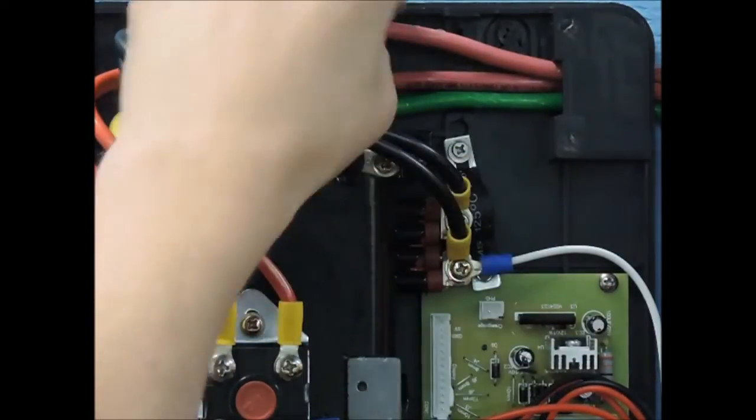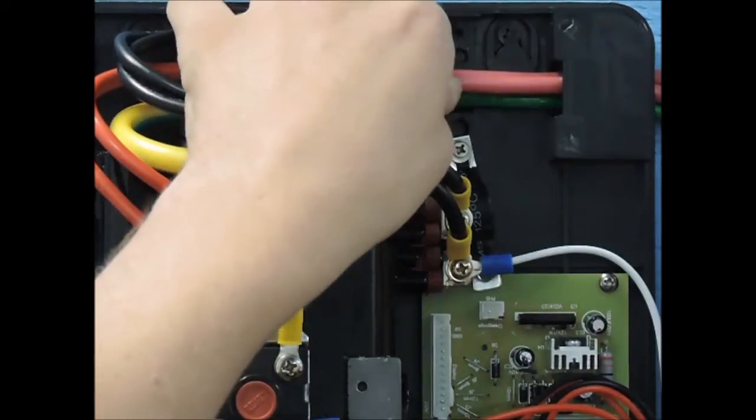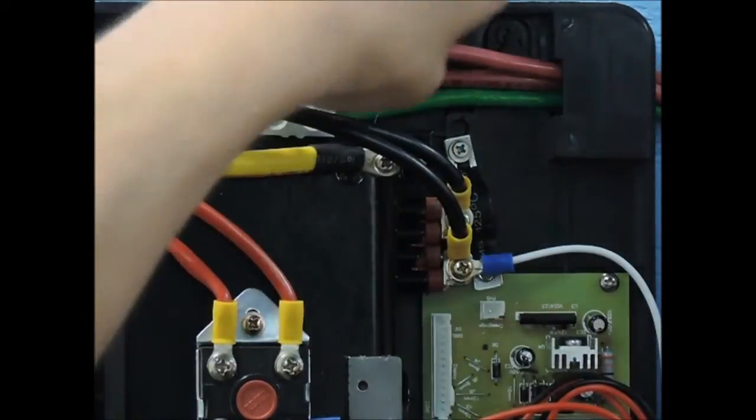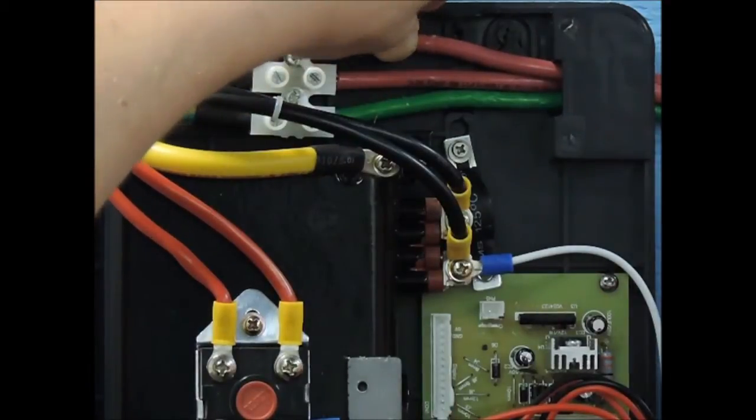Then, run one 6 gauge wire from each of the L1 and L2 connection points of the terminal block to the double pole 60 amp breaker at your panel.